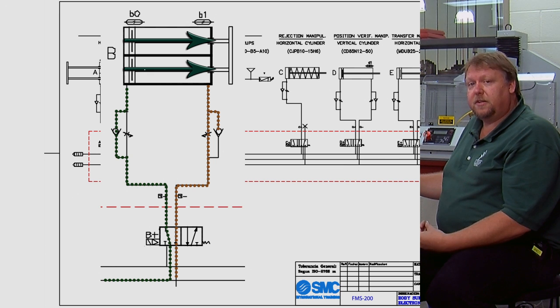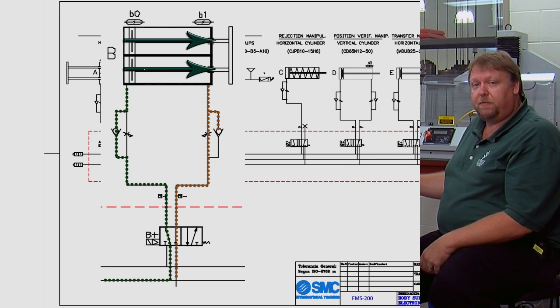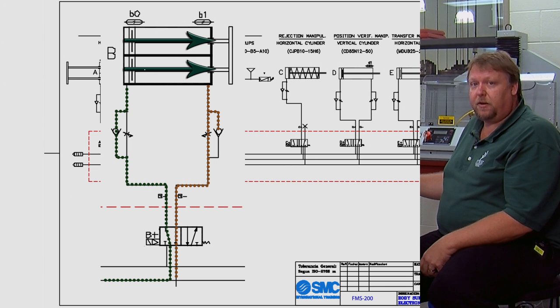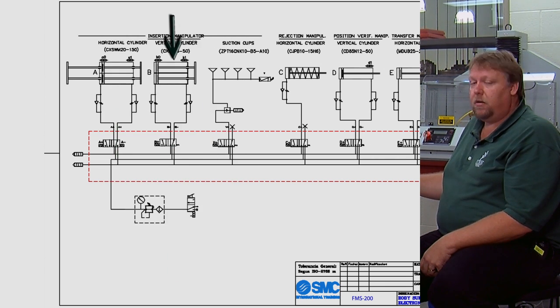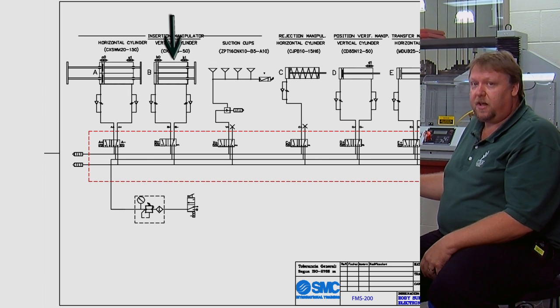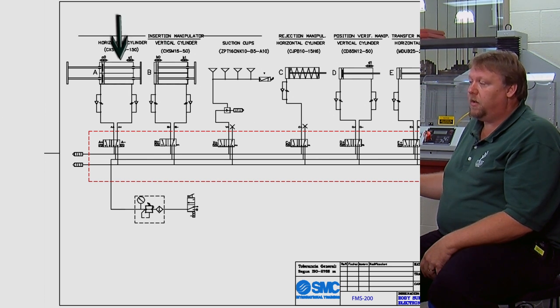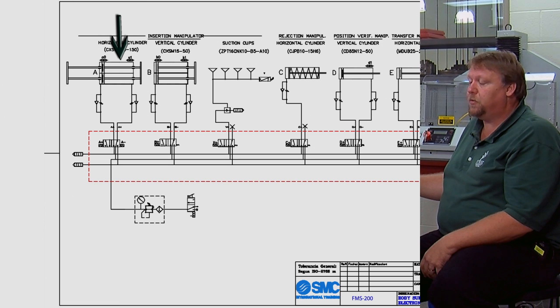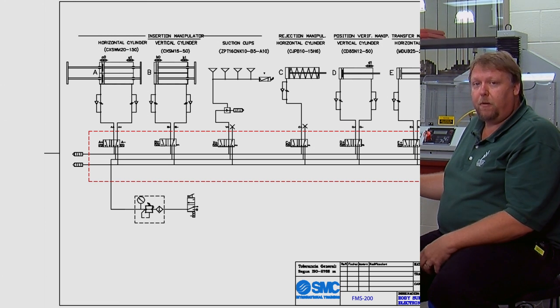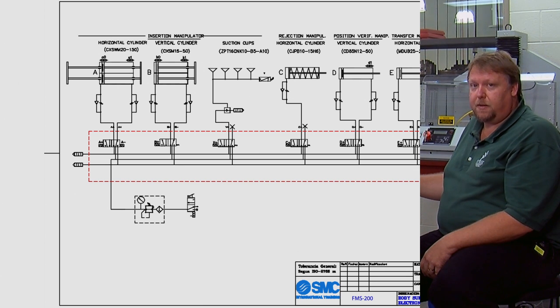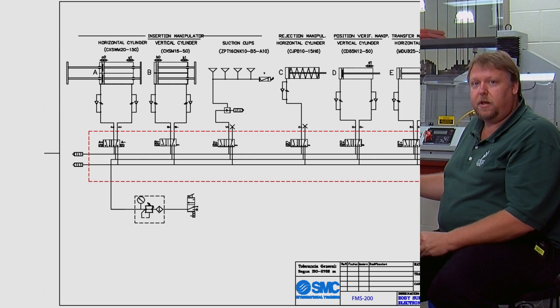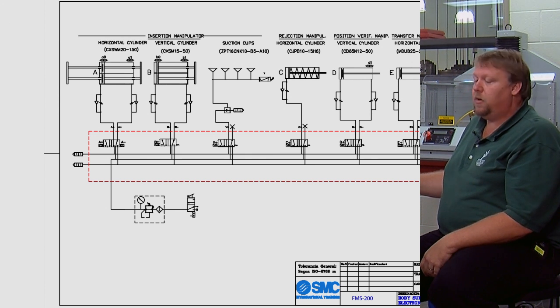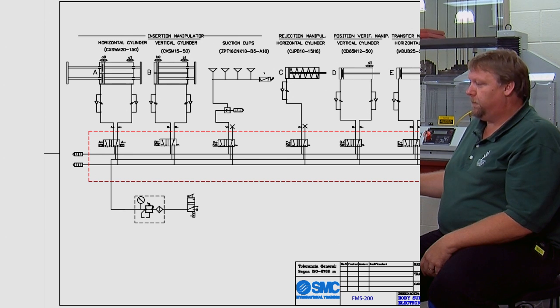So in order to get this cylinder to shift back the only thing that's required is we remove the electrical signal from the solenoid. So this cylinder here takes one signal to both extend and retract. Over here compared to the other cylinder which is the horizontal cylinder, it takes a signal to extend and a signal to retract. One thing that you need to be prepared for is to make sure that you don't turn on both solenoids at the same time. You will destroy the valve, it will cause it to overheat and it will burn the coil up. So you have to make sure that you prepare for that in your programming.